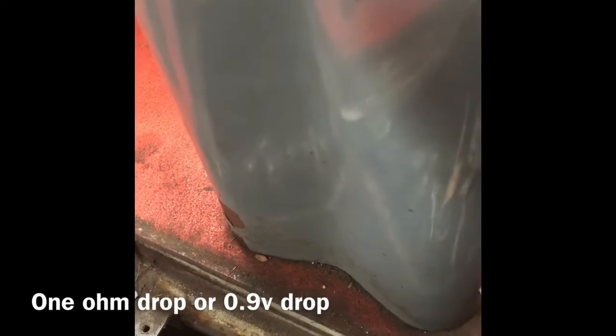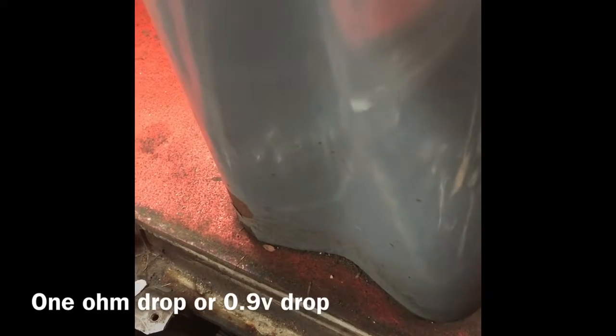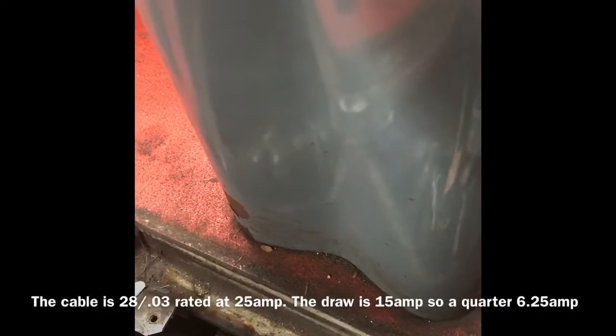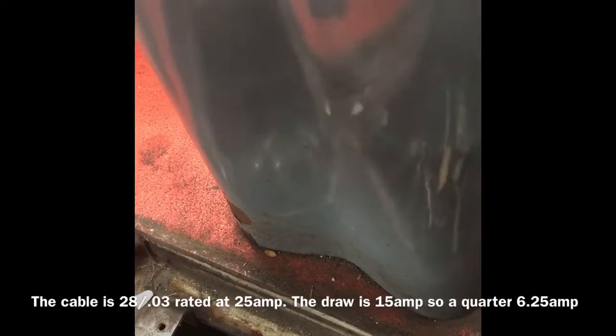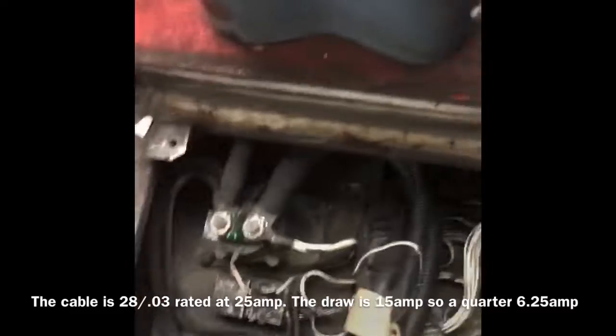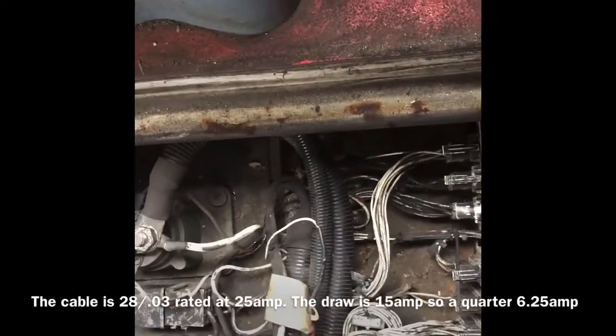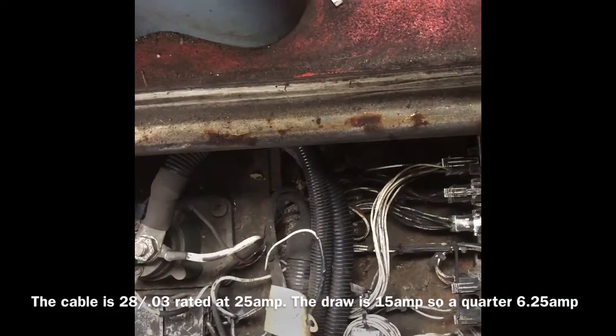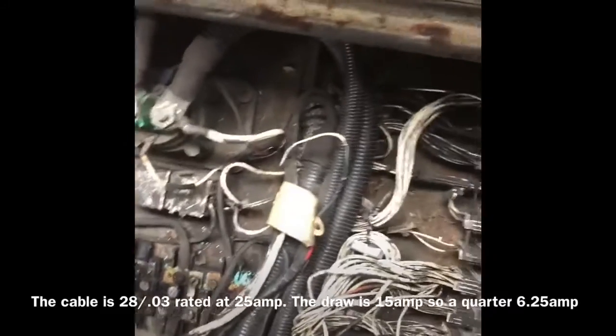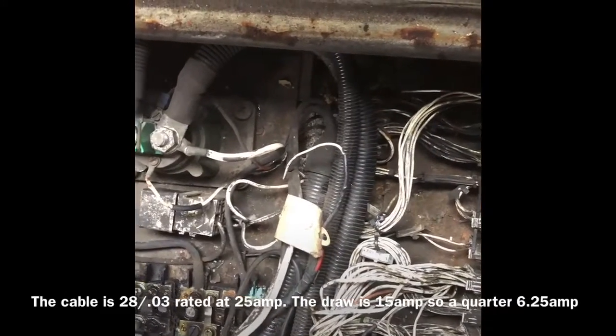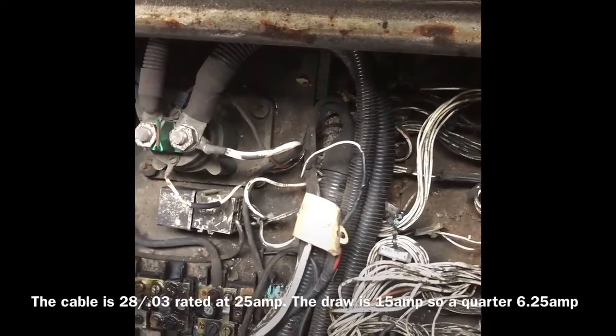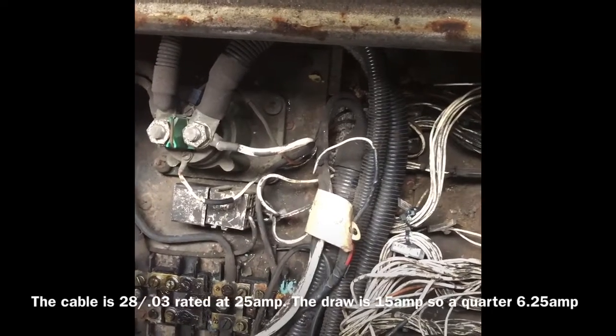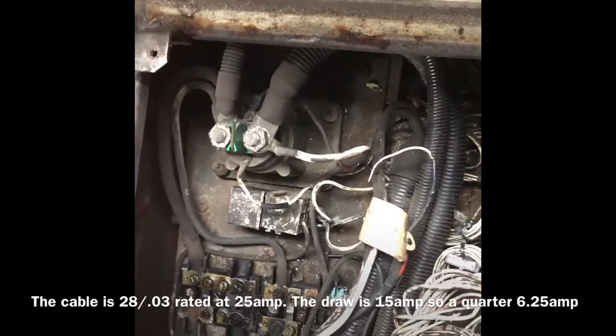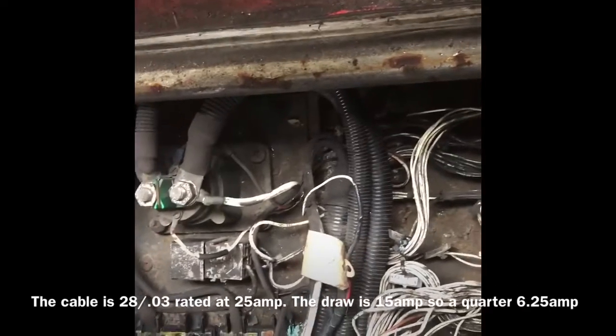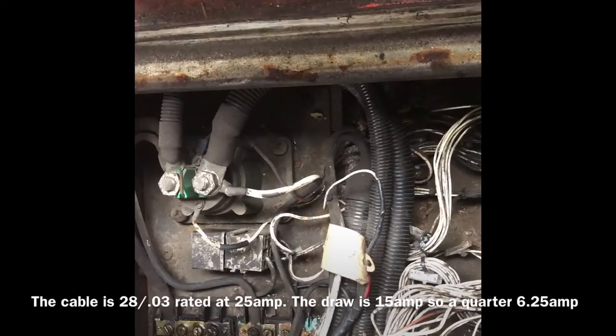Now, at some point, that is going to get worse. And once it's worse, you're going to end up with a problem where things cut out when you load them up. Now our load probe didn't actually pick up that a quarter of the connection is gone, nor did our resistance test.